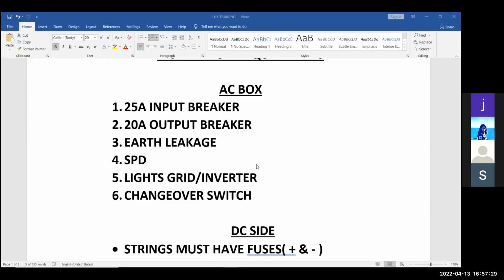Okay, now on SPDs, that's a surge protector device that we have this side. So on your SPDs, we recommend an SPD on the incoming line. So that means the power in line, your AC into your inverters. We recommend an SPD there. We don't ask everybody to do it, but as well an SPD on the line that's going out to the house as well for extra protection. But SPDs are fairly expensive, so we'll only recommend one on the Eskom side because the inverter will regulate what's coming out of it.